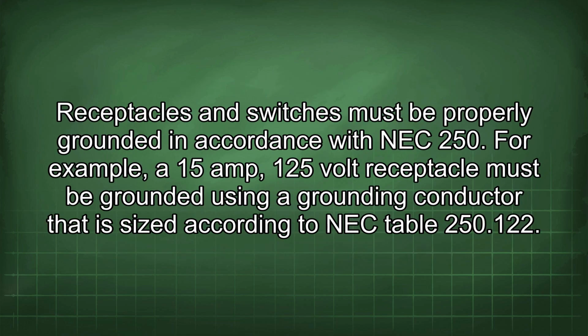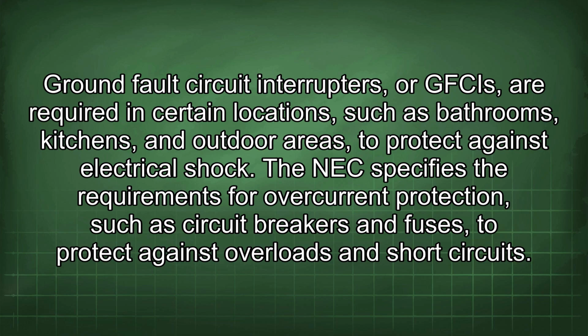Receptacles and switches must be properly grounded in accordance with NEC 250. For example, a 15 amp 125 volt receptacle must be grounded using a grounding conductor that is sized according to NEC Table 250.122. Ground fault circuit interrupters, or GFCIs, are required in certain locations, such as bathrooms, kitchens, and outdoor areas, to protect against electrical shock. The NEC specifies the requirements for overcurrent protection, such as circuit breakers and fuses, to protect against overload and short circuits.